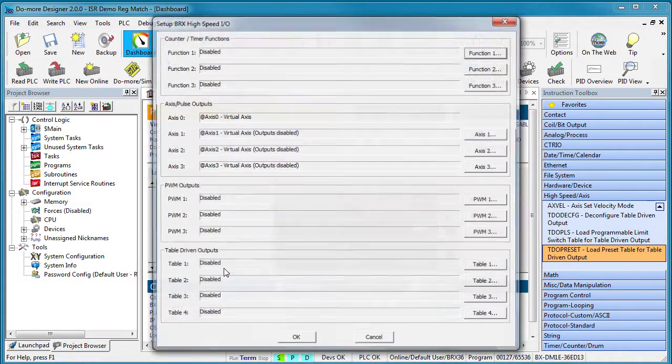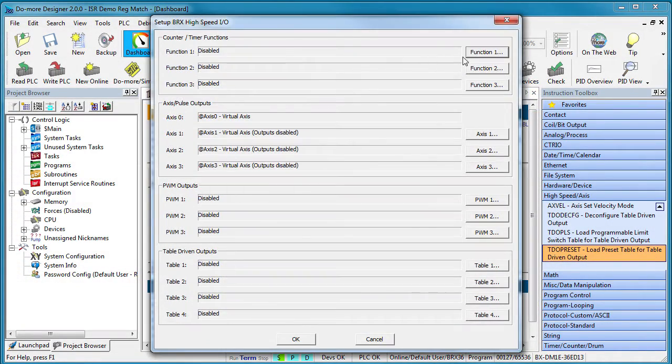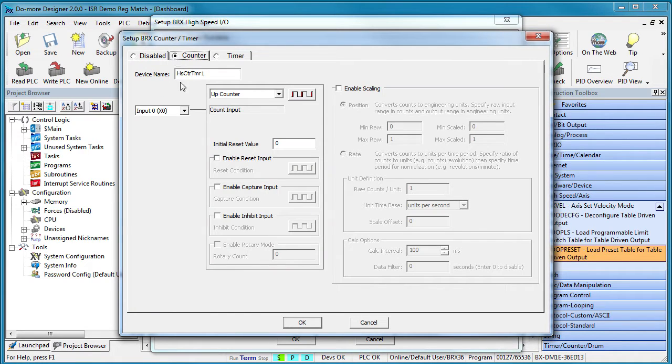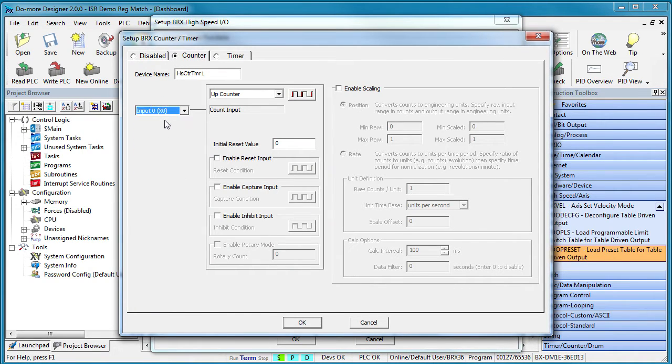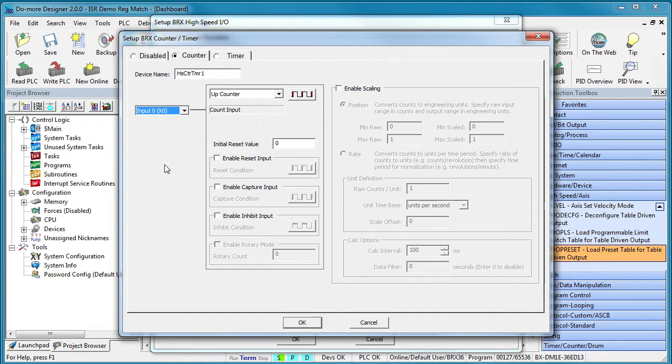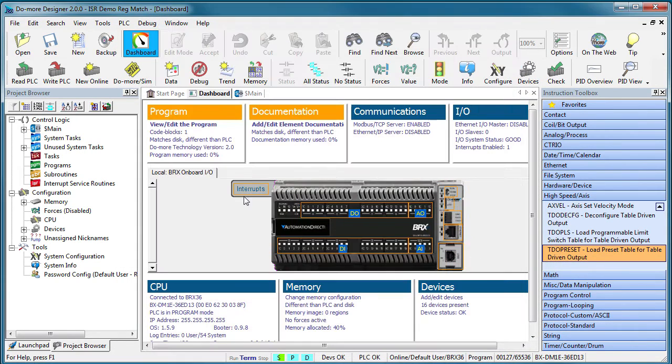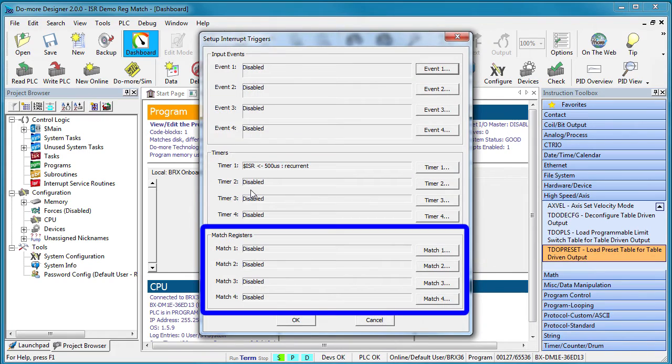Suppose you set up input X0 to be a high speed counter of some kind and you want to know when the count reaches some specific number. And you don't want to wait for the next scan to come around to find out about it when all the regular inputs get updated because it might be too late. Instead, you want to know about it right away so you can react accordingly. That smells like an interrupt thing, right? And that's what this Register Matching Interrupt option is all about.